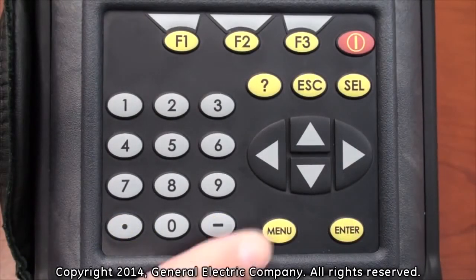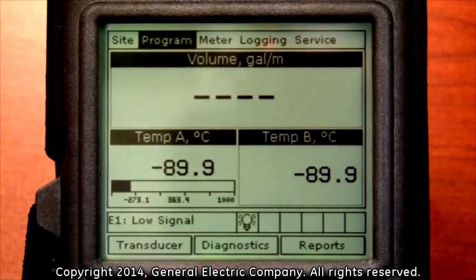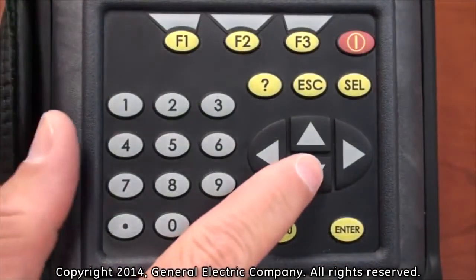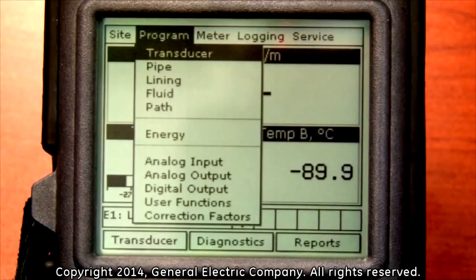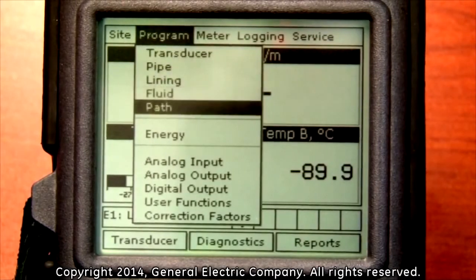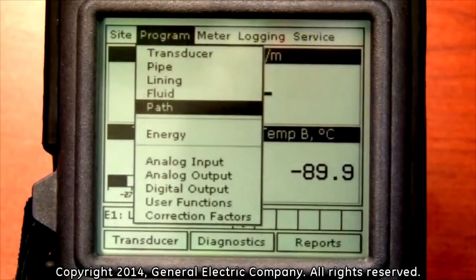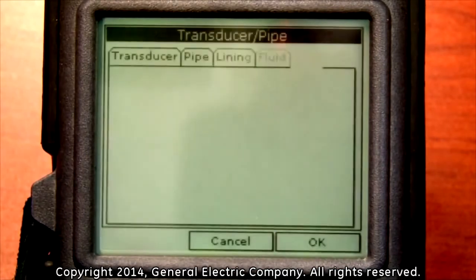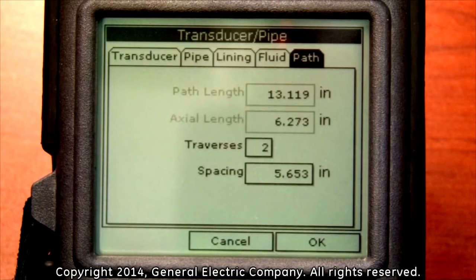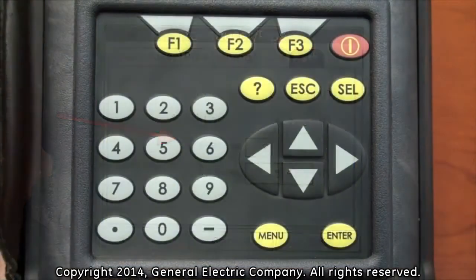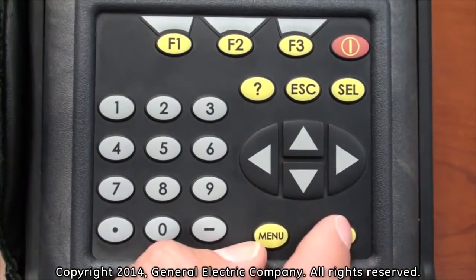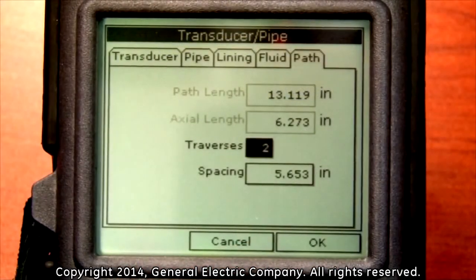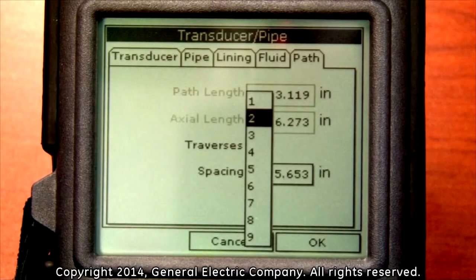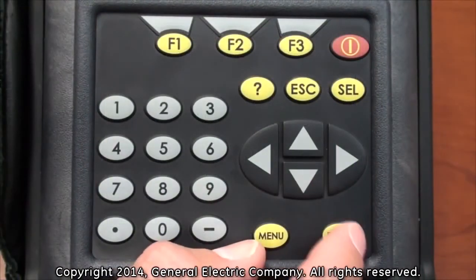Press the menu button to bring up the menu at the top of the screen. Use the arrow keys on the keypad to highlight the Program tab. Use the down arrow key to select Path and press the Enter button. For clamp-on installations, you must program the number of traverses, which is the number of times the sound wave travels through the fluid. Press the down arrow key to highlight the traverses input field and press Enter. This opens a new selection window that allows you to choose the number of traverses. Once you have chosen the number of traverses, press the Enter button.